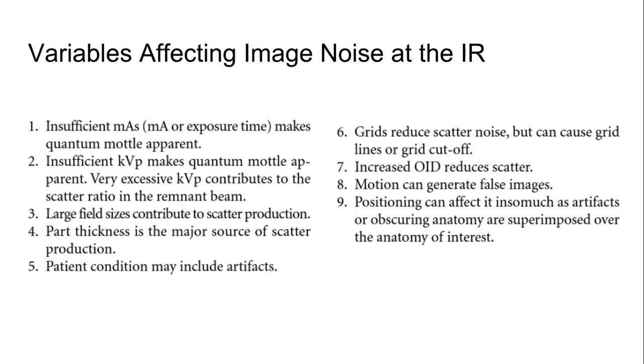How about number two? Insufficient KVP, which makes quantum mottle apparent. That is true. If we don't have enough KV, again, we're not going to get enough photons making it to the remnant beam and then to the image receptor. And again, you're not going to have enough data to utilize when the computer is doing its reconstruction. Now, excessive KV is going to also create noise in the form of scatter. So that's very excessive KV.